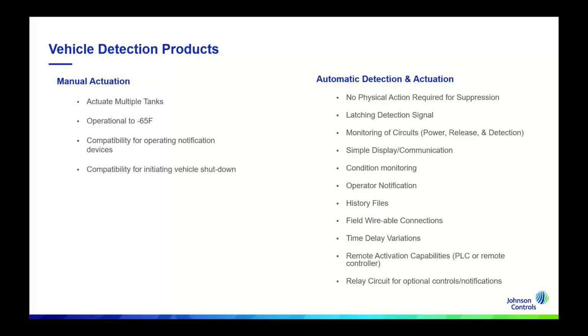If selecting a manual actuation system, look for one that can actuate multiple tanks from that single operation and that has an operating temperature range adequate for the hazard area. And also one that can operate notification devices such as a horn or strobe, as well as the compatibility to initiate shutdown devices.